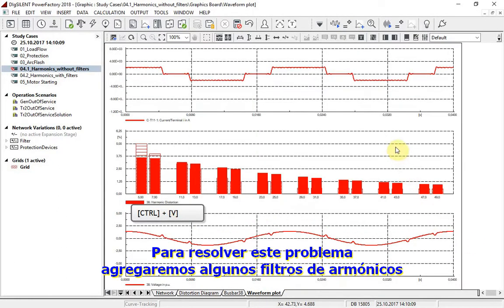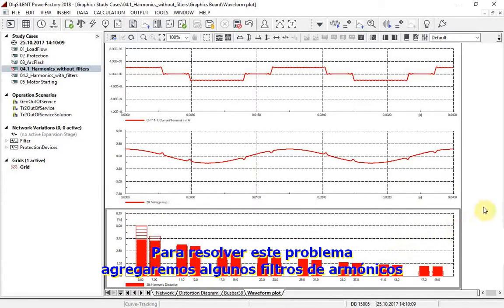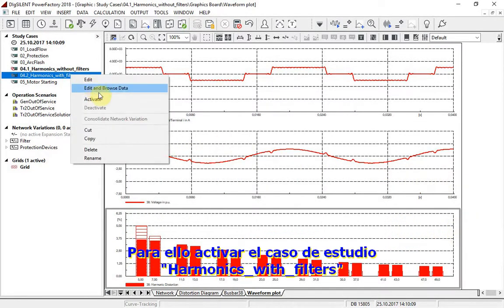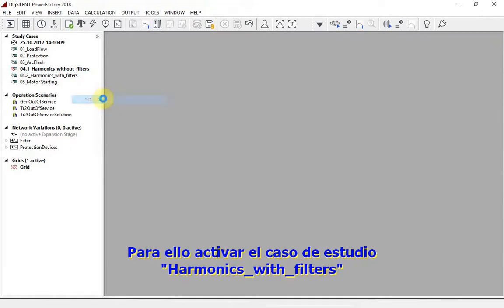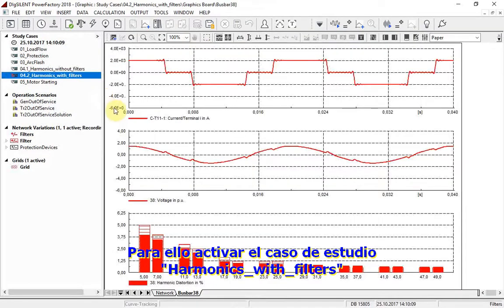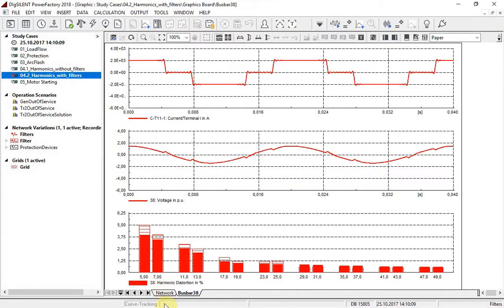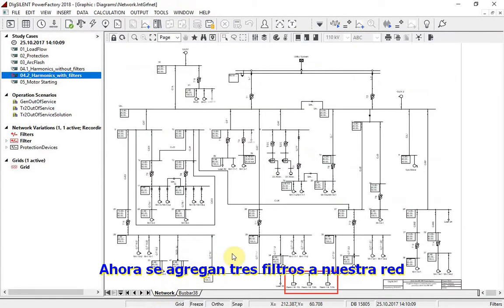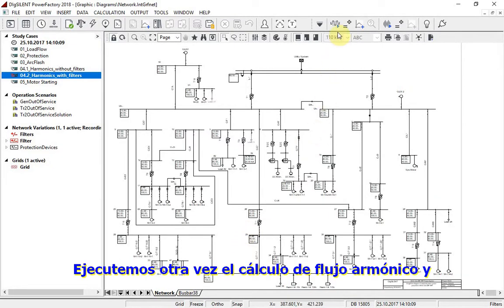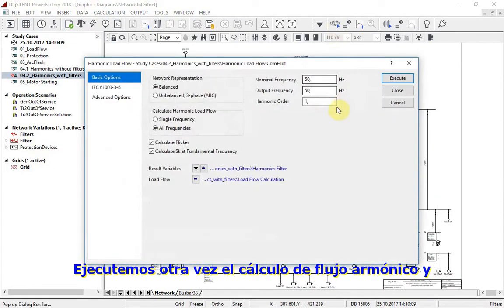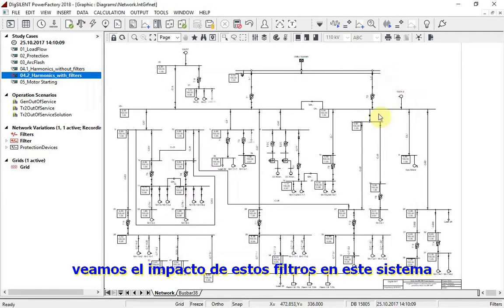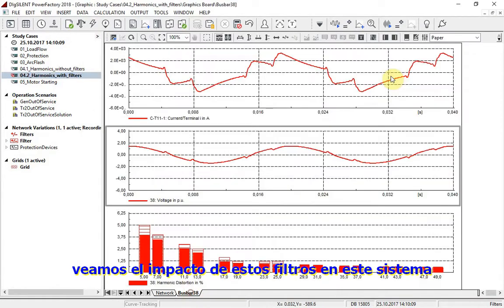In order to solve this problem, we will introduce some harmonic filters. For this, activate the study case Harmonics with Filters. Now three filters are being added to our network. Let us again run the harmonic load flow calculation and have a look at the impact of these filters on the system.